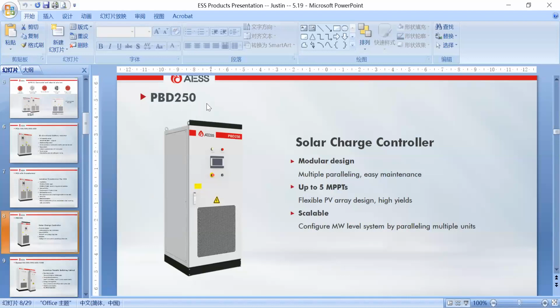That means the rated power is 250 kilowatt. Okay, and each PBD 250, we have up to 5 MPPTs. That means we can flexibly connect the array design, the PVs. Okay, and how many PBD do we need normally in application? It really depends on how large your solar power is. Okay, for example, if you have 1 megawatt solar power, solar panels, then a very simple calculation, we need 4 of 250.